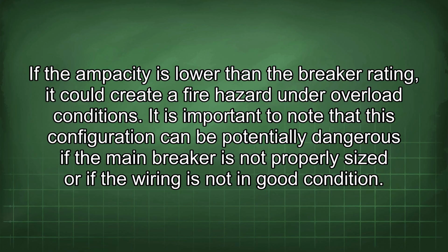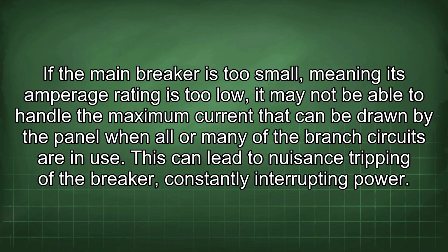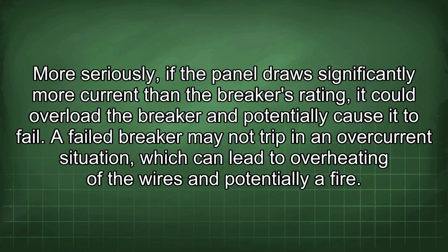It is important to note that this configuration can be potentially dangerous if the main breaker is not properly sized or if the wiring is not in good condition. If the main breaker is too small, meaning its amperage rating is too low, it may not be able to handle the maximum current that can be drawn by the panel when all or many of the branch circuits are in use. This can lead to nuisance tripping of the breaker, constantly interrupting power. More seriously, if the panel draws significantly more current than the breaker's rating, it could overload the breaker and potentially cause it to fail. A failed breaker may not trip in an overcurrent situation, which can lead to overheating of the wires and potentially a fire.